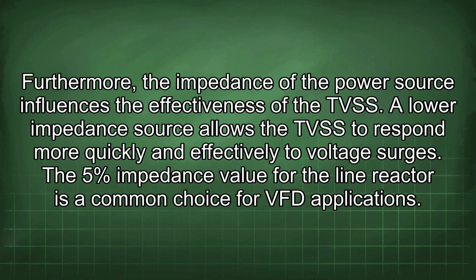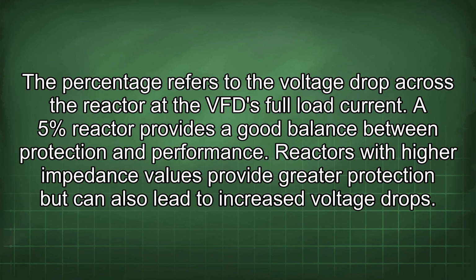Furthermore, the impedance of the power source influences the effectiveness of the TVSS. A lower impedance source allows the TVSS to respond more quickly and effectively to voltage surges. The 5% impedance value for the line reactor is a common choice for VFD applications. The percentage refers to the voltage drop across the reactor at the VFD full load current. A 5% reactor provides a good balance between protection and performance.